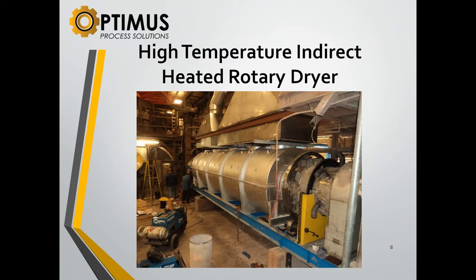This is a high temperature indirect heat dryer. The first dryers that we talked about, the steam tube dryer, is an indirect heat dryer utilizing both radiant and conductive heat. The direct heat dryers are more of a convective heat dryer, and this is pretty much a radiant heat dryer. We have the rotating cylinder going through the combustion chamber, and there are burners on the opposite side. They're actually heating refractory inside this combustion chamber. That refractory radiates its heat through the shell, and then the shell imparts its heat conductively through and into the product.